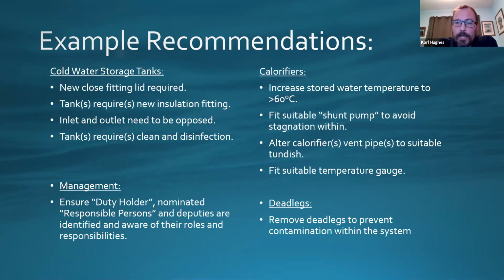One of the things now as well is you'll see vent pipes over the hot cold water storage tank from the calorifiers. Now what they're asking is that these be sent to a separate tundish. So the idea is if the calorifier starts venting hot water, the last place you want hot water to be venting into is a cold water storage tank. One place I went to, I went into the roof space, and the tank had turned into a sphere, a ball, because they changed the hot water system to mains pressure, and it was acting like a radiator. So the cold water storage tank in the roof space was literally running hot scalding water through it, and that was a cold water storage tank.